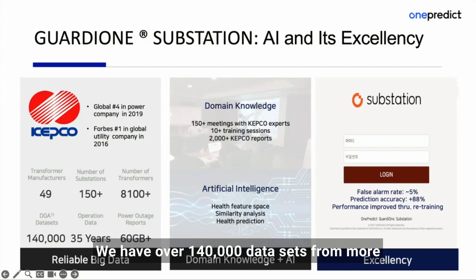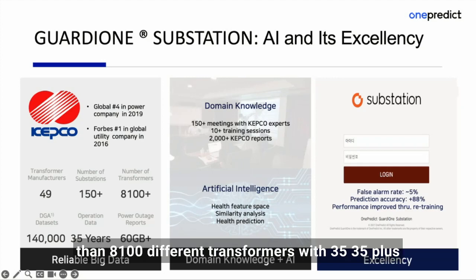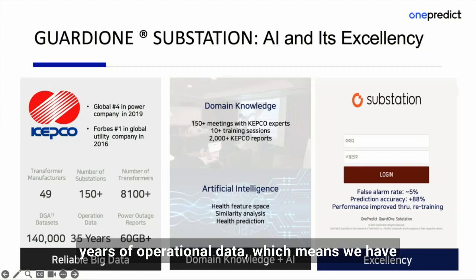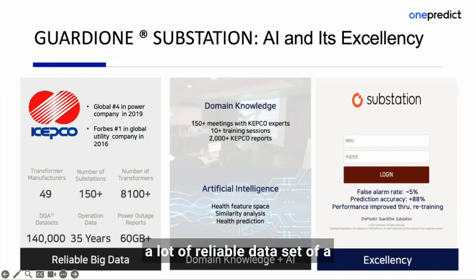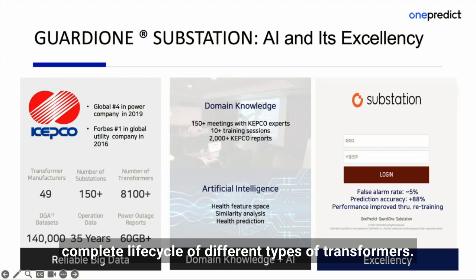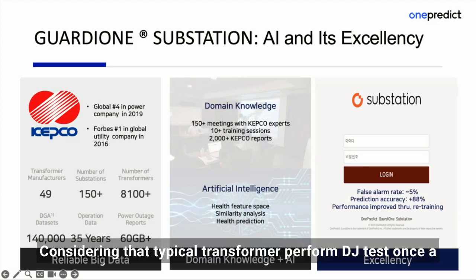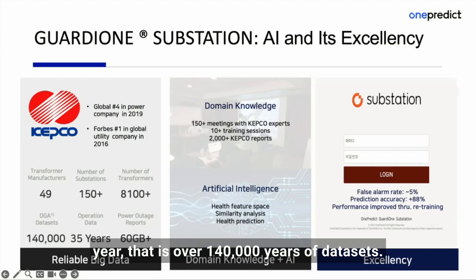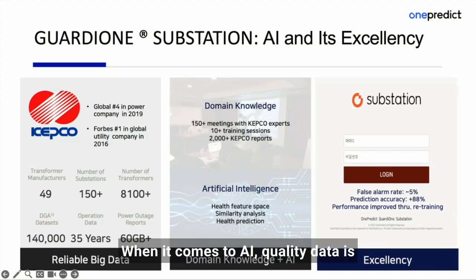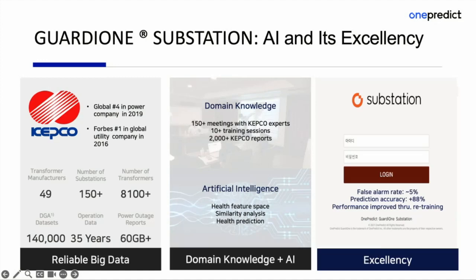companies, we have over 140,000 data sets from more than 8,100 different transformers with 35 plus years of operation data, which means we have a lot of reliable data sets of a complete life cycle of different types of transformers. Considering that a typical transformer performs a DGA test once a year, that is over 140,000 years of data sets. When it comes to AI, quality data is the most important factor, and we have a lot.